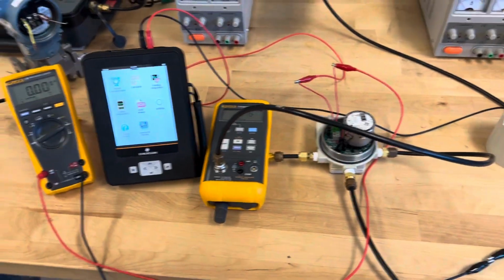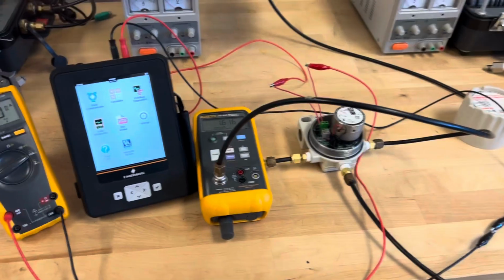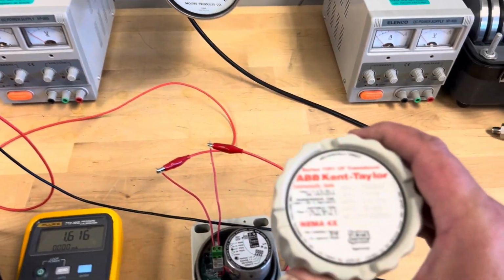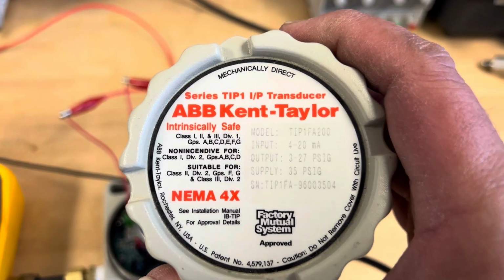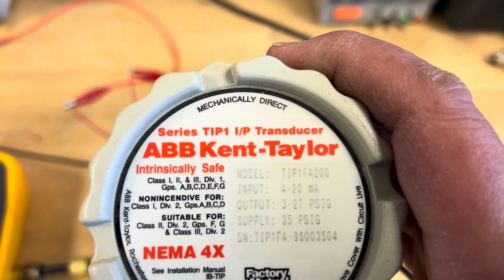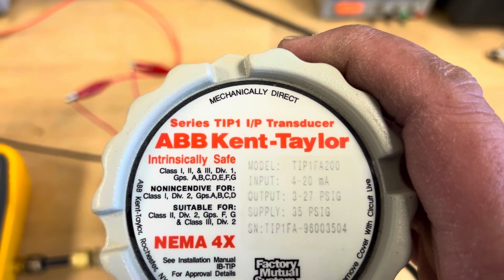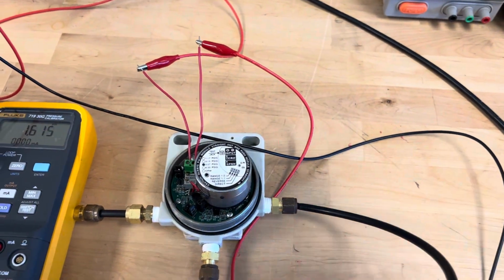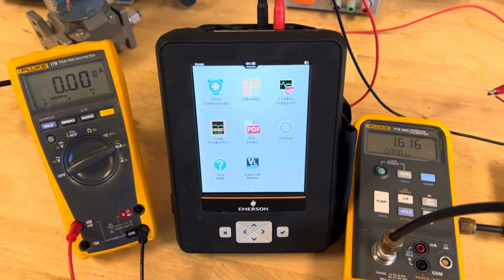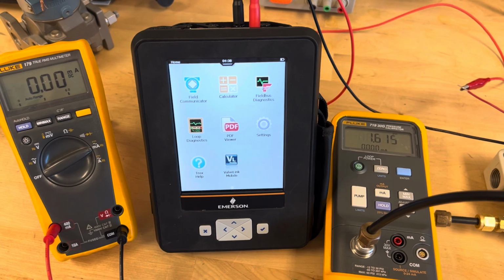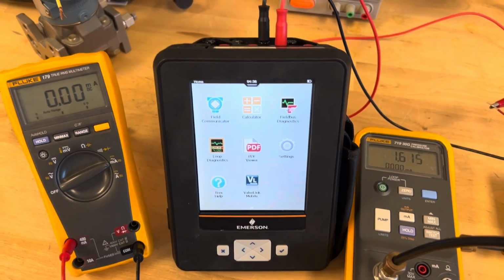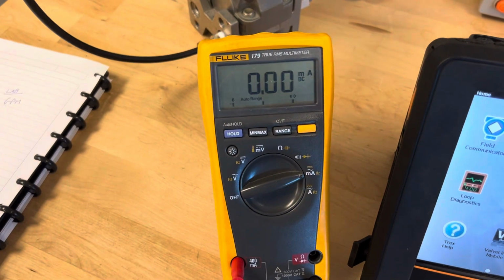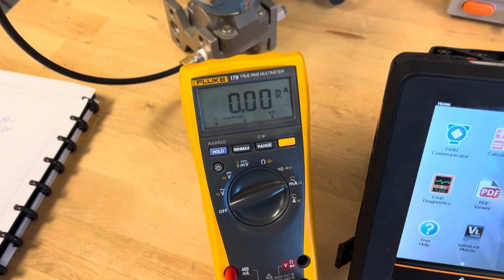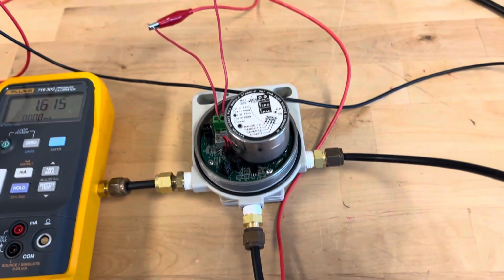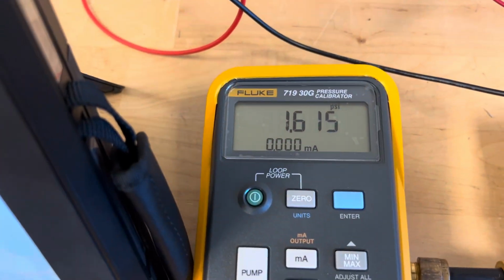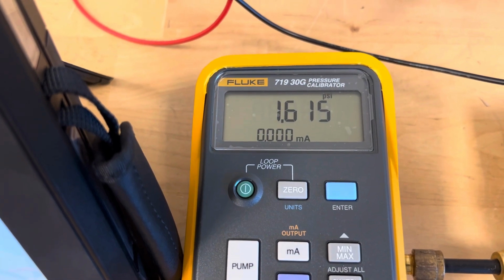Today I'm going to be performing a calibration on an I2P transducer. It is an ABB Kent Taylor series TIP1 I/P transducer. I'm going to be providing my milliamp signal from my Trex communicator. I have in series with the Trex communicator a Fluke 179 so that I can read my milliamp signal. And the pressure coming out of my transducer I'm going to be reading with a Fluke 719, and it's set to PSI.